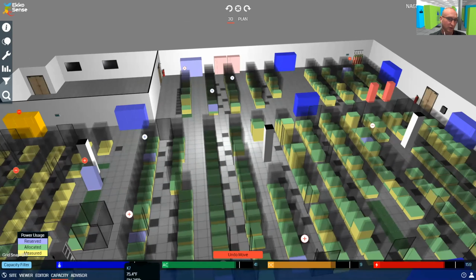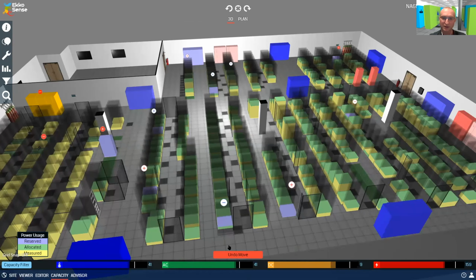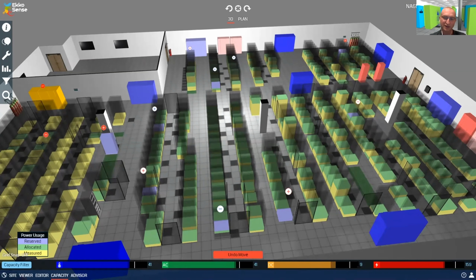At the bottom you get a very quick overview, the 4 key points of making capacity changes. You can see what your cooling capacity is within the site, so you instantly know you've got 41 kilowatts available for cooling capacity. You've got UPS AC and DC capacity in that room, and you can mix AC and DC in the same room and understand how that goes back at system level. If we make a change in this particular room, it will affect other rooms too, so you don't over allocate, since it all goes back to the centralized system. Then you can see how much that's going to affect capacity available at site level.